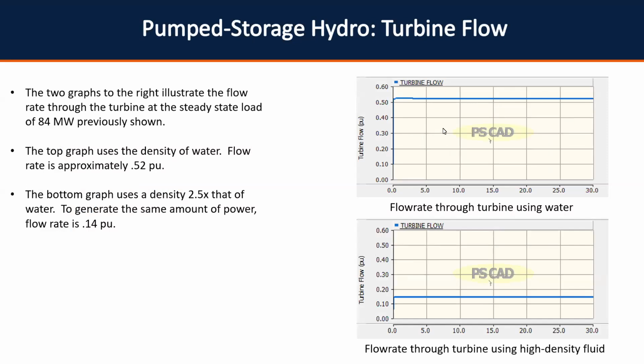I want to compare the flow rate. The top graph here is turbine flow rate with fluid density equal to 1, so it's water. We're at about 0.52. The bottom is with that more dense 2.5 times gain on there. I should have mentioned before, this is all operating at 84 MVA, so both cases have the same output from the generator, but the flow rate drops from 0.52 to 0.14.